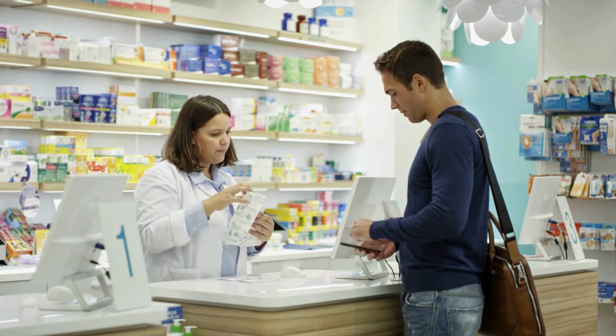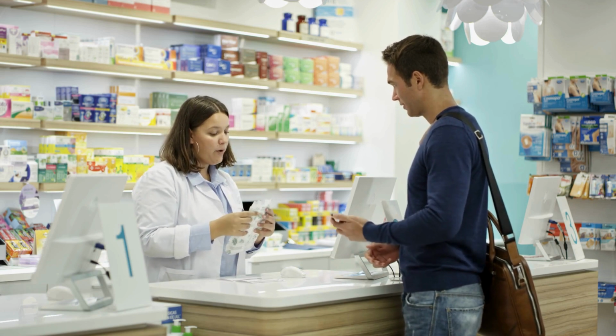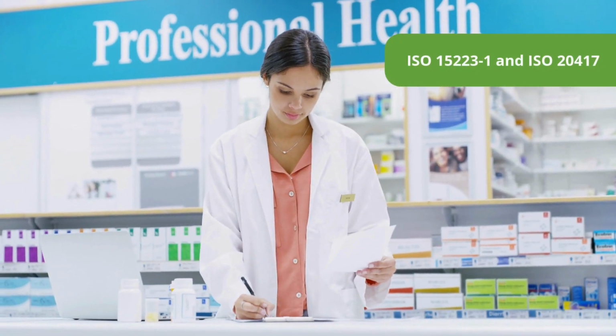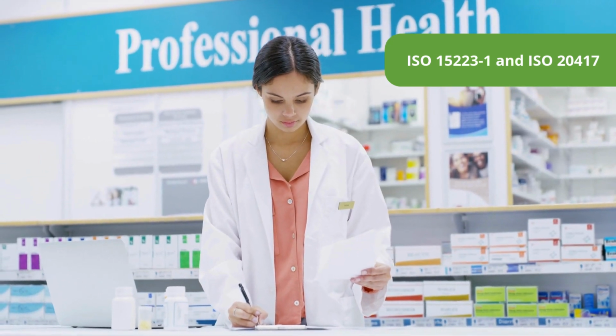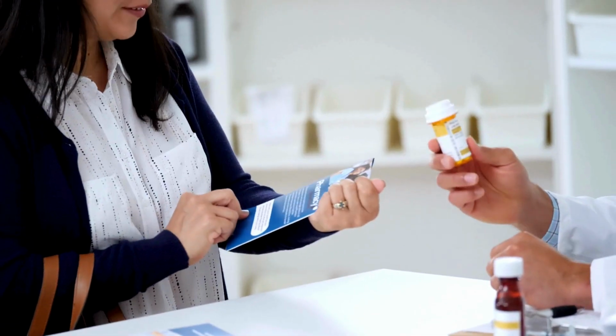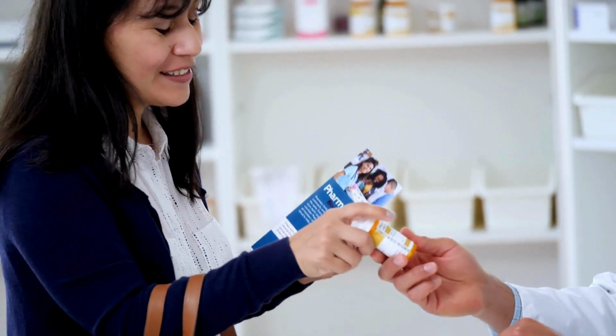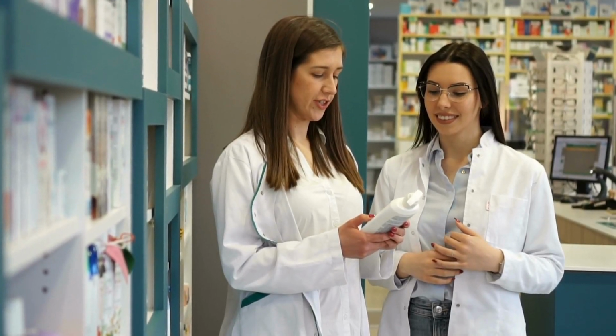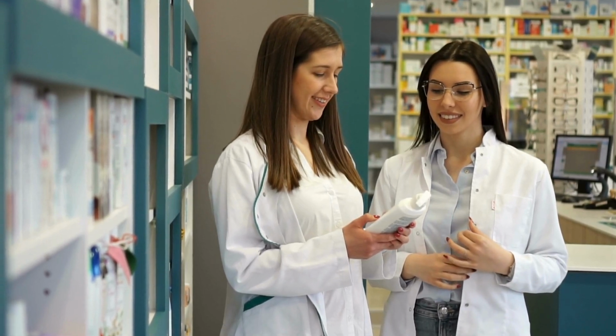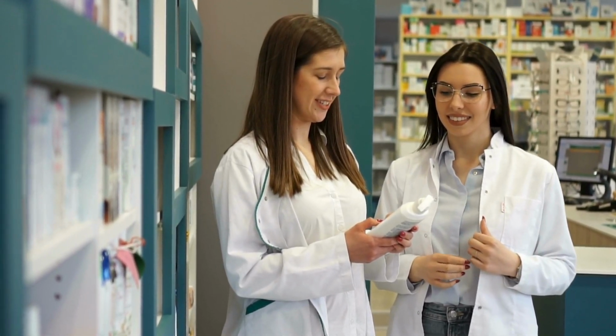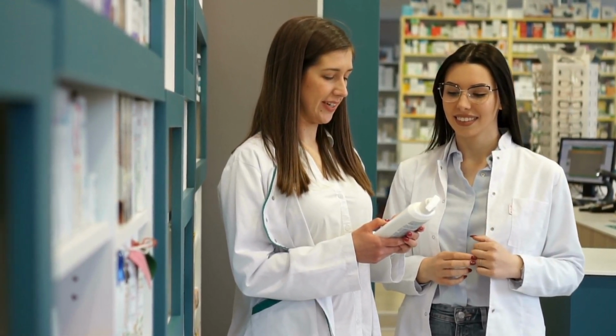So, how do you get it right? Here are a few tips. 1. Familiarize yourself with ISO 15223-1 and ISO 20417 for harmonized labeling standards. 2. Use a clear design template and labeling software to ensure consistency. 3. Regularly review and update your labels to reflect any product or regulatory changes. 4. Test your labels for durability and usability under real-world conditions.